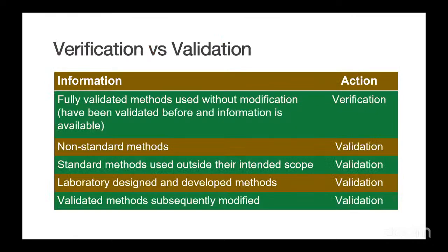So verification versus validation. A fully validated method used without modification, where information is available that it has been validated before, is called verification. When you are doing a non-standard method, that is validation.